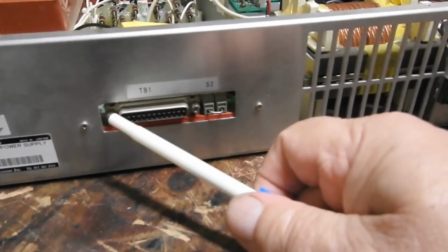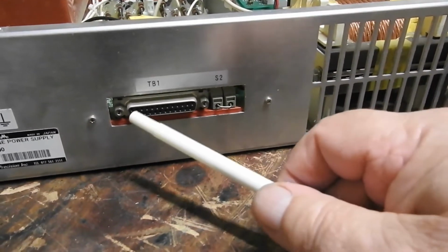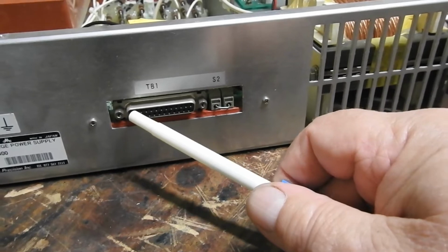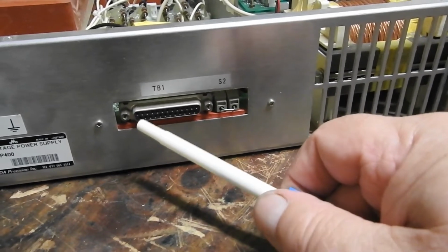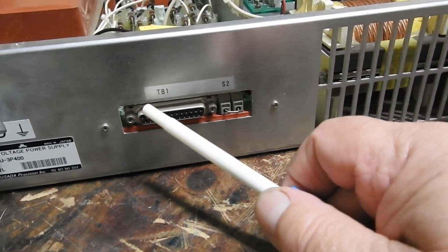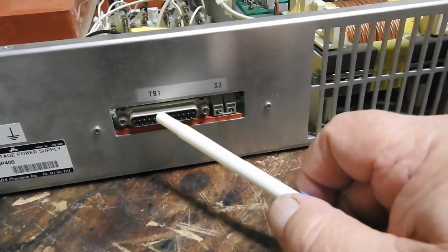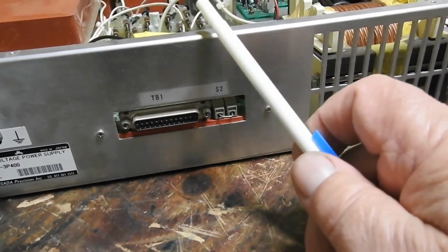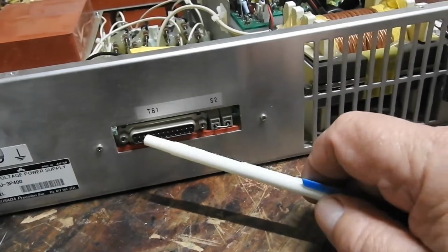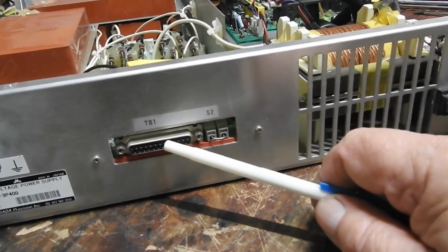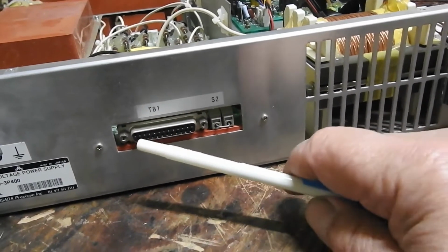On the back there is the instruction manual, shows what this is for. There's inputs for controlling the voltage and current, just 0 to 10 volts goes through the full range. There's also signals coming out, 0 to 10 volts, indicating what the current and voltage are. There's a 10.24 volt reference output which you can use for the voltage and current control inputs.